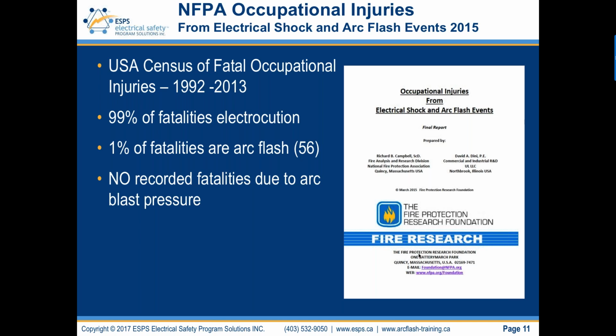But there's the stats. 99% of fatalities were shock that led to electrocution in the last 20 years. 1% of fatalities were arc flash related burn injuries that weren't survived. The important bullet is there's no recorded fatalities due to arc blast pressure, which is an important discussion point with respect to our assessment of the arc blast pressure hazard as a secondary effect of arc flash. So again, statistics help us. They help us interpret information and manage it. So I encourage you to get a copy of this and put that into your resource toolbox.